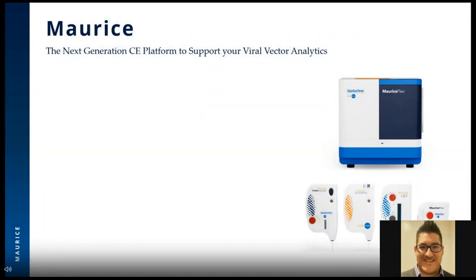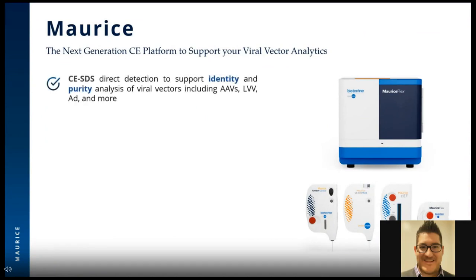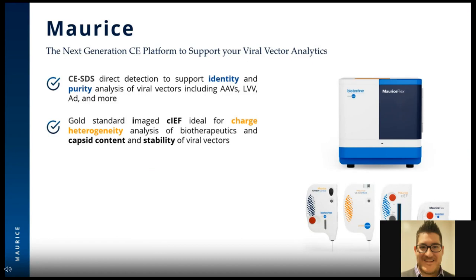Maurice is the next generation capillary electrophoresis platform to support viral vector analytics and address these challenges. Maurice has two separation modes: CE-SDS, which separates proteins by size and can be used for viral vector identity and purity analysis; and the gold standard imaged cIEF, which is ideal for charge heterogeneity analysis of biotherapeutics, and specifically for capsid content and stability analysis of viral vectors.